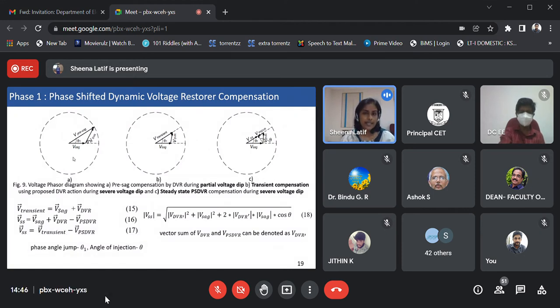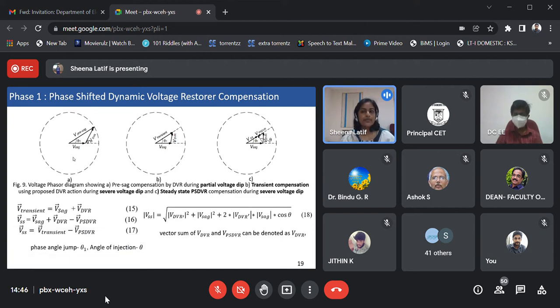During transient mode, the same DVR mode is activated, but since the sag voltage has fallen to a severely low condition, it is not able to compensate the voltage to its pre-sag value, but the phase angle correction takes place. Afterwards, in the steady state mode, the transient voltage is injected with a voltage VPS-DVR in the opposite direction such that a steady state voltage VSS is obtained, which is less than VSAG in magnitude, but phase angle correction takes place.